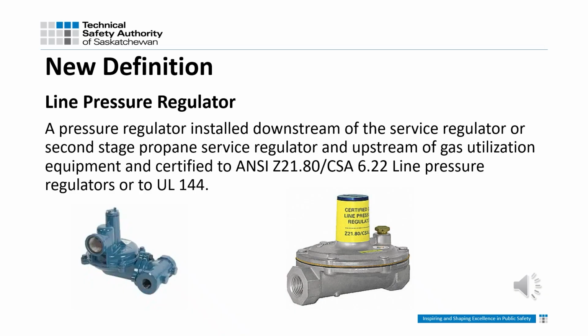Some of these regulators have restrictions on vent length. If you need to pipe the relief to the outside or away from a source of ignition, exceeding this length or the number of fittings may void its certification. This is the certified regulator that is required on 90% of all propane jobs moving forward in the province of Saskatchewan.